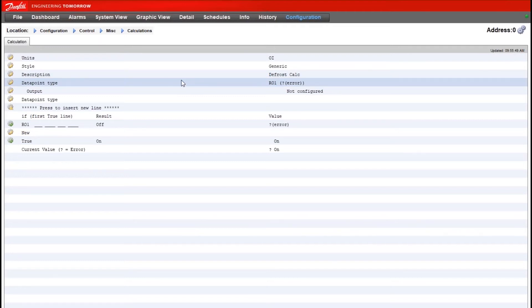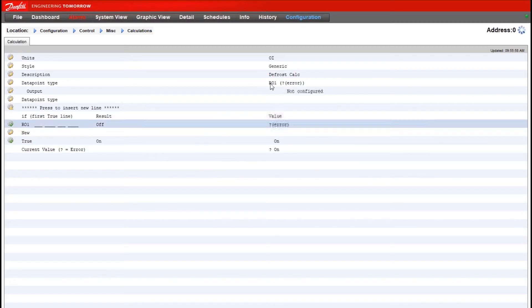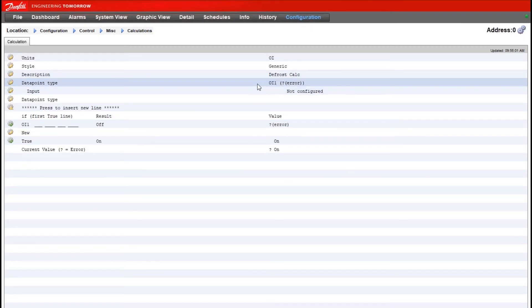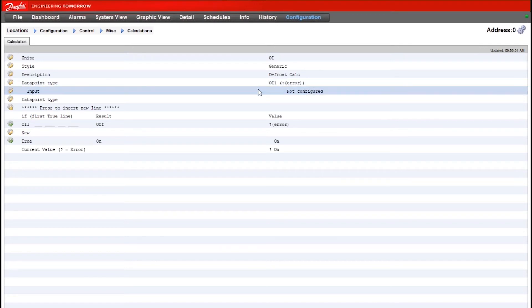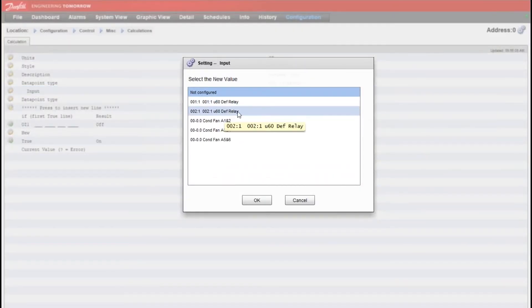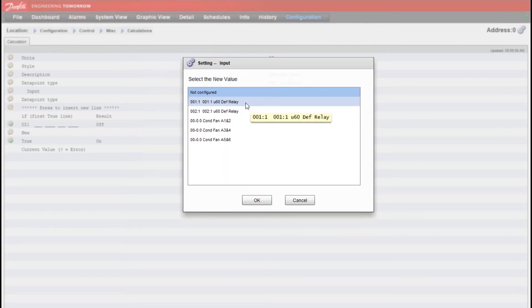And then we get into our data point types. Now data point type, keep in mind that even though we're looking at a physical relay on the case controller, the system manager is importing it as just a digital input. So we want to make sure data point type is set to OI and not RO. Once I've done that you can now see that the defrost relays that I imported from the case controllers are listed here as options for an input.